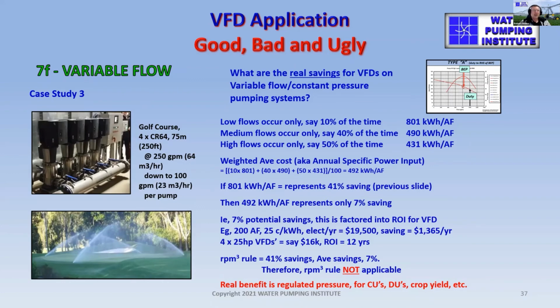Well, yes, at the slowest flow, you may save that amount of energy, but how much time are those pumps pumping at that low flow? Let's look at a typical breakdown. You might find the highest flows are where the system duty point is. You find that a typical turf system may be pumping at the highest flows at least 50% of the time. And I've calculated, in the previous example, that's 431 kilowatt hours per acre feet. It might spend 40% at medium flow rates. That's only 490 kilowatt hours per acre feet. But the really low flow rates, where you can get the best VFD energy savings, it's only pumping 10% of the time, sometimes even less than that.